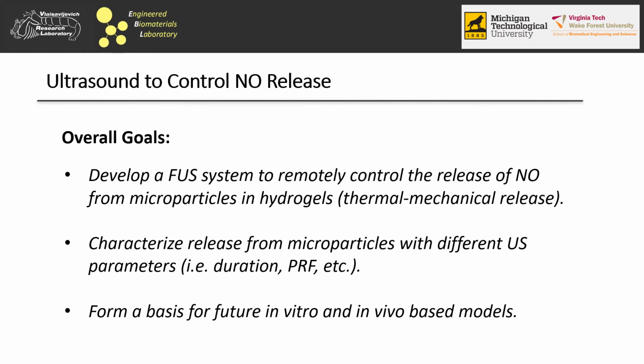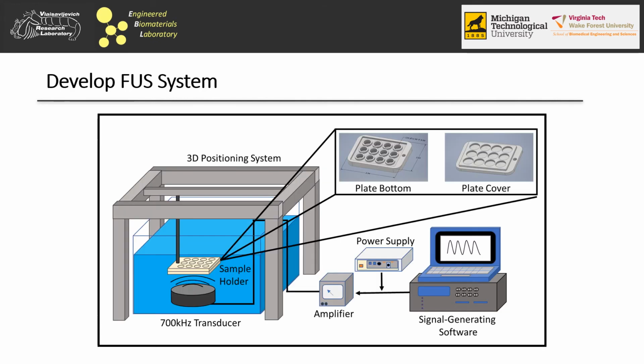After verifying that NO release from our materials had the potential to modulate MMP activity at constant temperatures, our goals were to develop a focused ultrasound system to thermally and mechanically control NO release from our microparticles remotely, characterize the release of NO from our hydrogels using different focused ultrasound parameters, and to form a basis for future in vitro and in vivo models. Here's an overview of the focused ultrasound system we utilize at Virginia Tech for our studies, using a 3D positioning system, 3D printed acoustically transparent sample holders, and a 700 kHz Histosonics transducer.